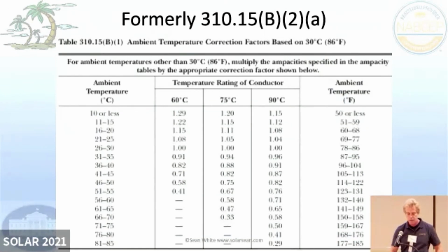And so they changed 310.15(B)(2)(a). That's ambient temperature correction factors. If I had a 90°C rated wire and the temperature in degrees Celsius was 35, then I'm going to have a 0.96 rating factor. So I'm only going to be able to carry 96% of the current. That's how you use this table. And this 90°C is rated for the insulation. That's how the insulation is rated. And then this is the outdoor temperature. 30°C is 86°F, 40 is 104, and 50 is 122. So just to give you some examples, that's how you use that table.